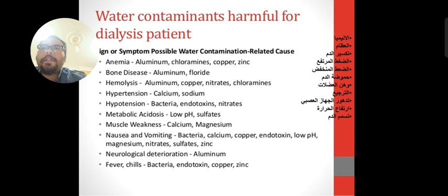Every day and every shift of dialysis we assess the water treatment unit by measuring what's called TDS and chloride. TDS means total dissolved solids in the water. We take a sample of water and put this part of the equipment in the water, then we read the reading here. The TDS reading must be less than 30 to be sure the total dissolved solids in the water is in the normal range.